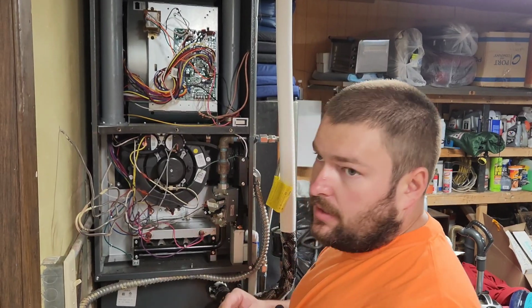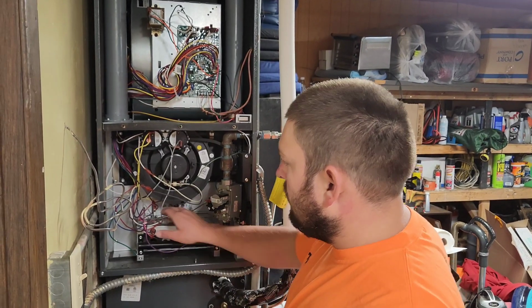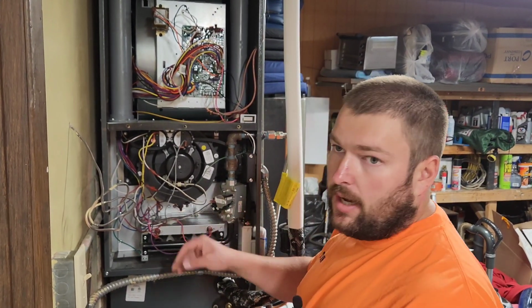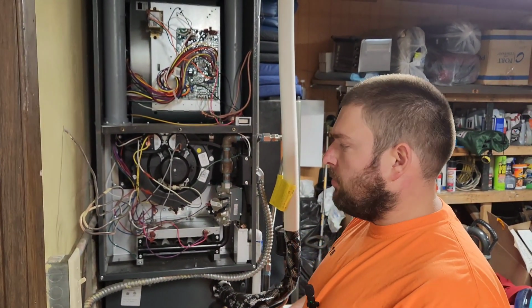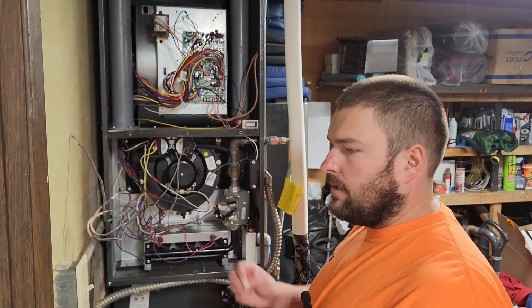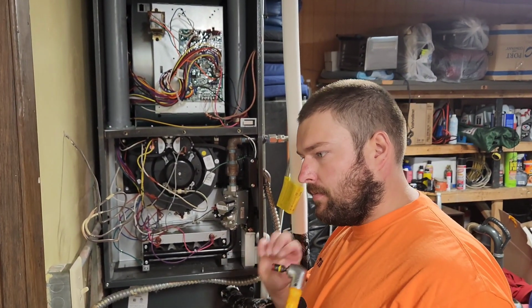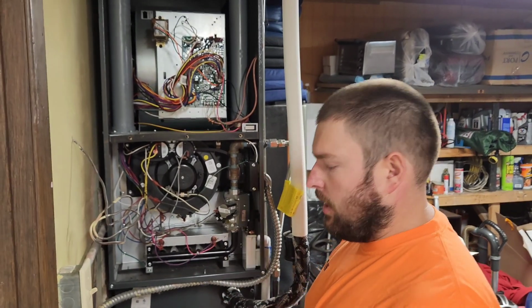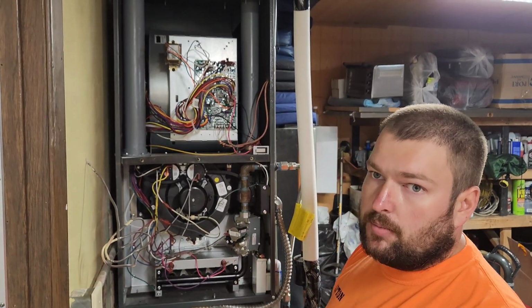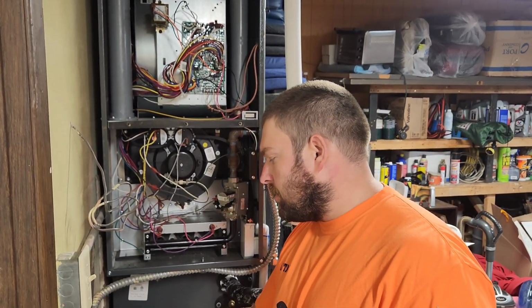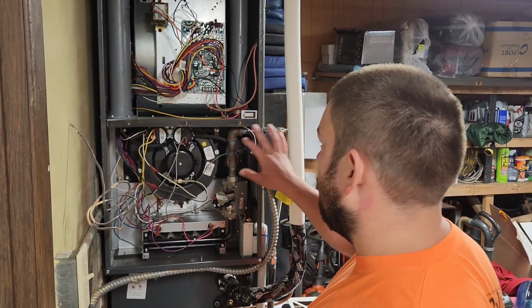One of the big maintenance items here that a tech will do is take your flame sensor, pull it out and actually clean it. That's kind of a big maintenance item. When that thing gets dirty, it'll prevent your flames from staying on, and your furnace won't come on in the middle of winter. What we're going to do is shut the power off completely, even though I have the doors off.